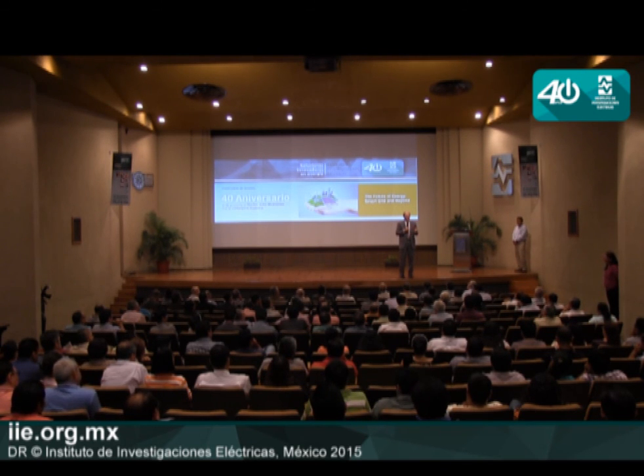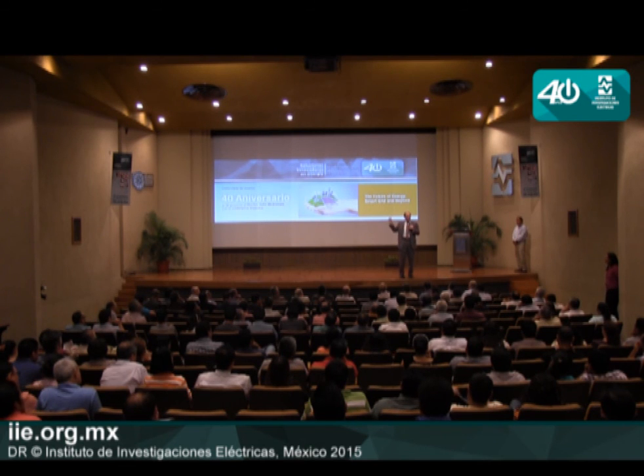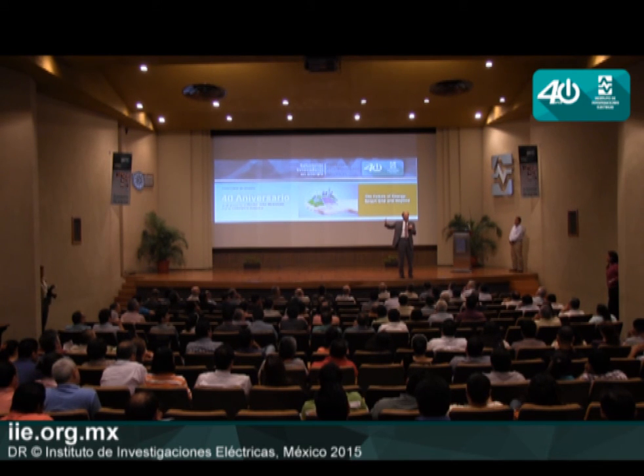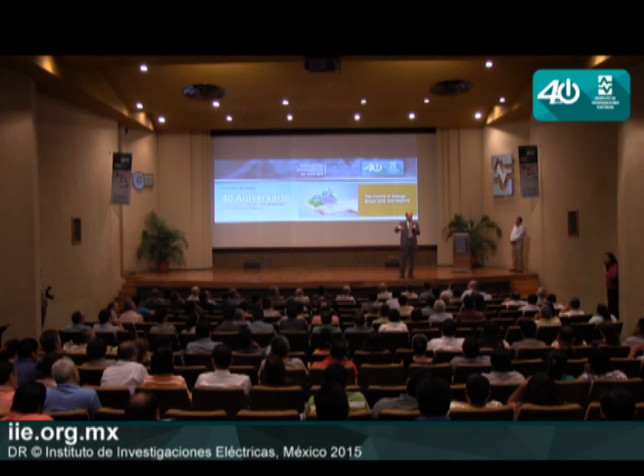So to me, we should move to dynamic ratings - the ratings of all the equipment on the grid should be based on actual conditions, and we know the actual conditions based on sensors. Now, one of the challenges with distribution: we can put a DMS at the utility with all these fancy application programs, but you can only optimize what you know is happening in the field. When you have a lot of substations with no automation, you have no data coming back - you're blind, and the feeders are even worse.